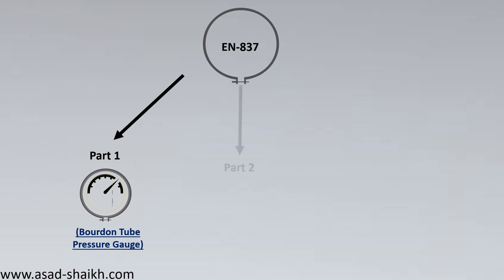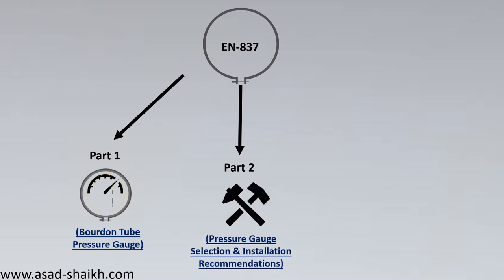EN 837 Part 2 deals with installation and selection. For very low pressure applications, you may need a diaphragm or capsule type pressure gauge; for medium to high pressure, a Bourdon tube is used. A proper table is provided recommending which type of pressure gauge to use at which pressure. It also covers different installation types — whether mounted on a panel, on a tee, dial size visibility, and more.